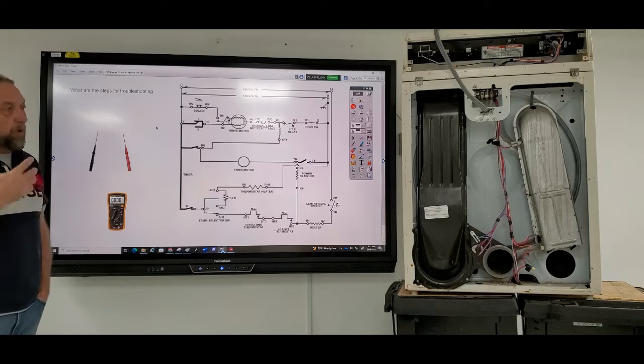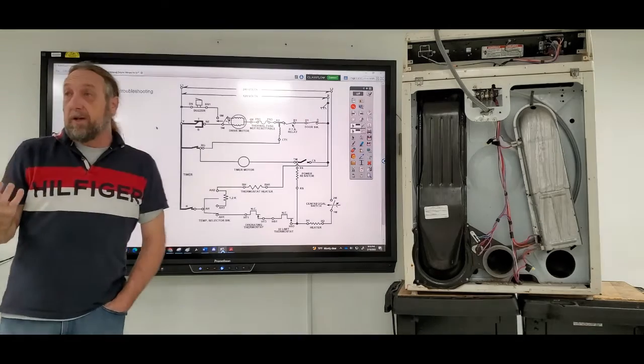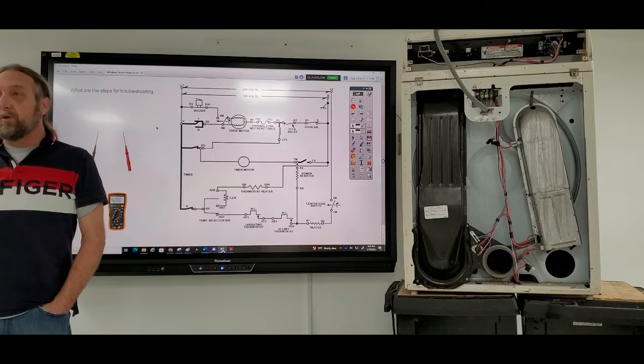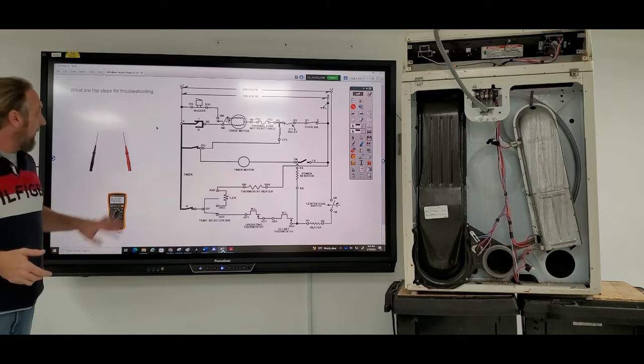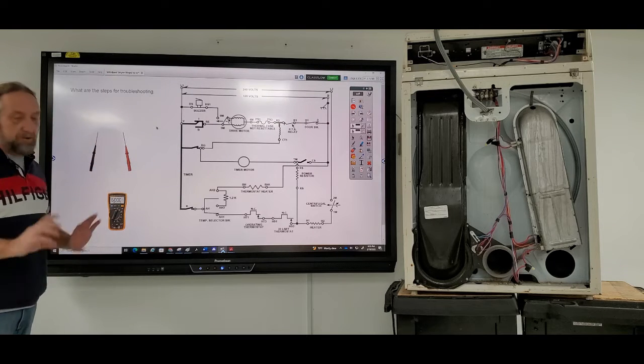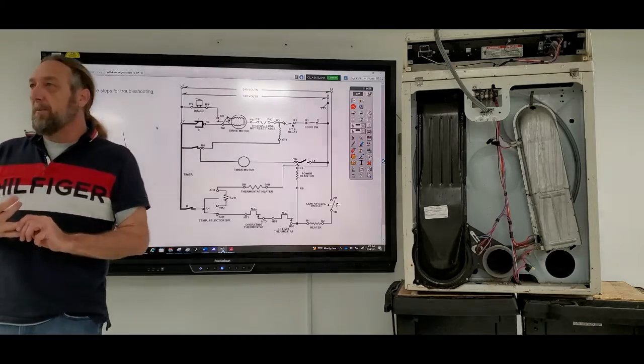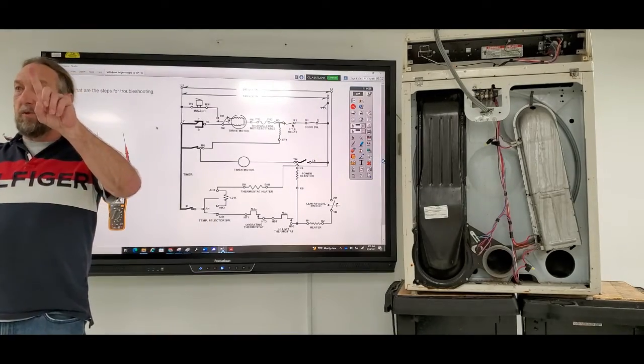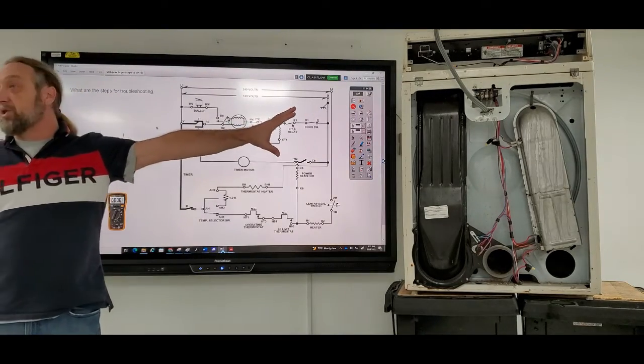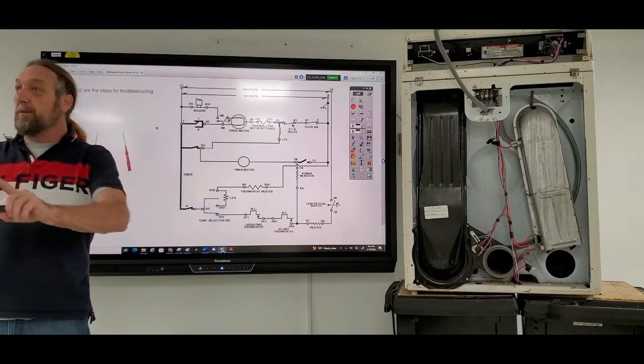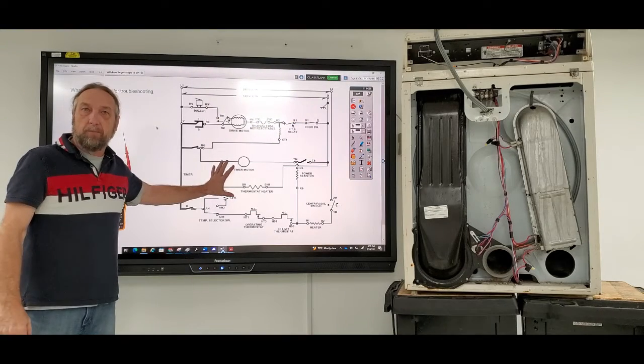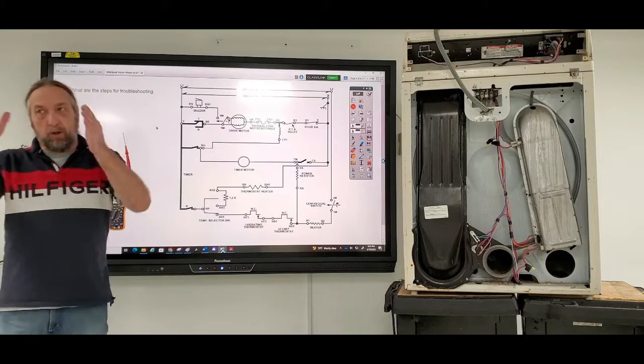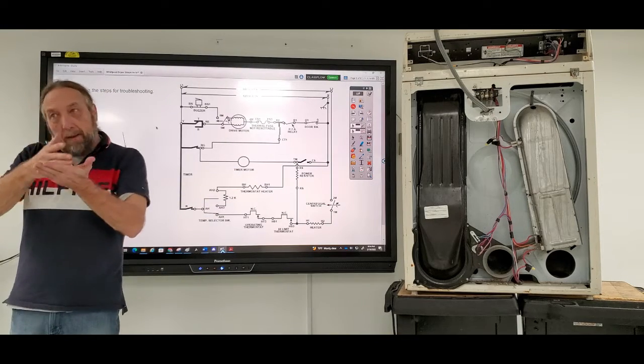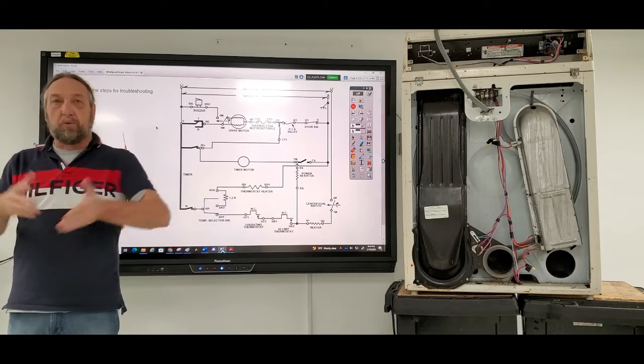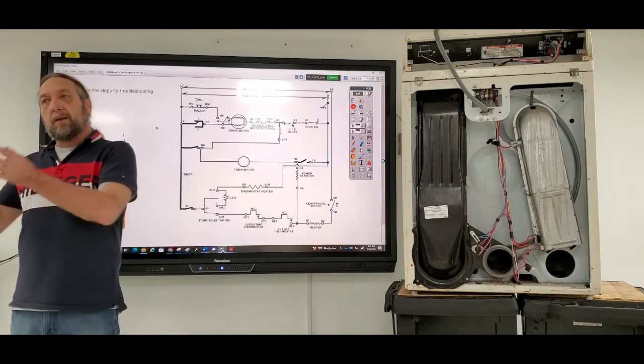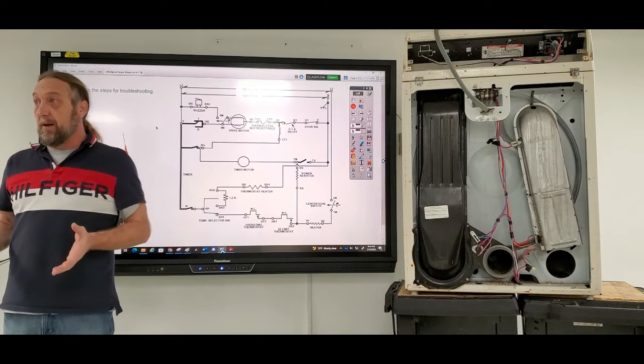When we go to a dryer that's not working, we have to make tests. So I have these meter leads here, and this meter is just there for show, but I can put the meter leads on test points, then put them on the machine at the same point they would be on the diagram. If you could look at the diagram and map out how the current's flowing through that circuit, then you would know how to test it out.